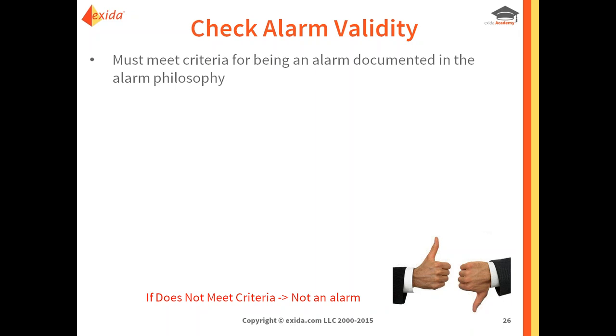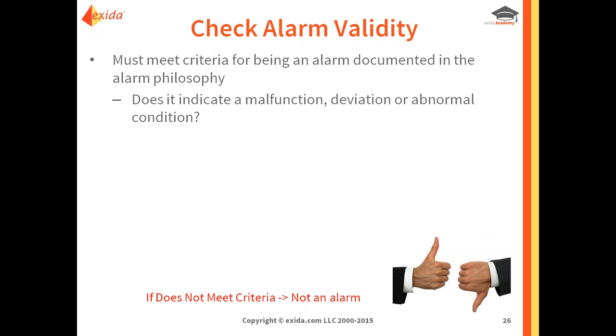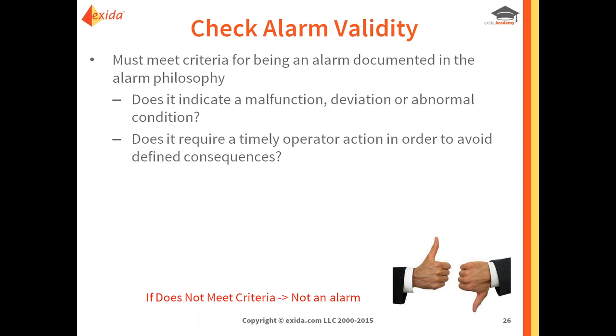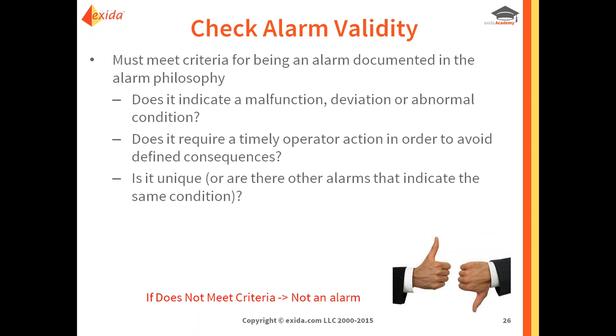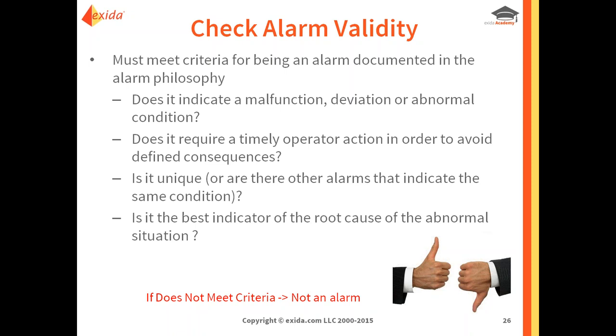How do we determine whether an alarm is valid? Using the definition of an alarm, we apply go/no-go criteria. First: does the alarm indicate a malfunction, deviation, or abnormal condition? If you can't answer yes, it is not an alarm. Second: does it require a timely operator action to avoid defined consequences? Again, if the answer is no, it should not be an alarm. Additionally: is it unique, or are there other alarms that are better indicators of the root cause?